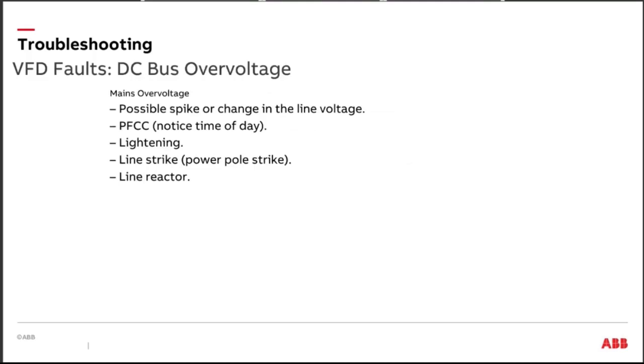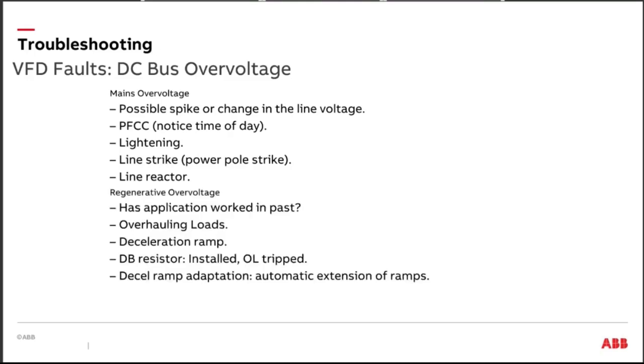Over voltage, very common trip. Power factor correction capacitors, lightning strikes. On the weekends, we've had through the years, I've seen sites where the voltage goes high on the weekends. It'll travel up to 500, 515 volts and cause a problem with the over voltage. If you're in the fan world, the HVAC world, if I've got a large fan and I'm trying to bring it down too fast, that's a real easy way of causing an over voltage, controlled by the deceleration ramp. If I'm in industrial, have I tripped my circuit breaker or my fusing in my dynamic braking circuit?